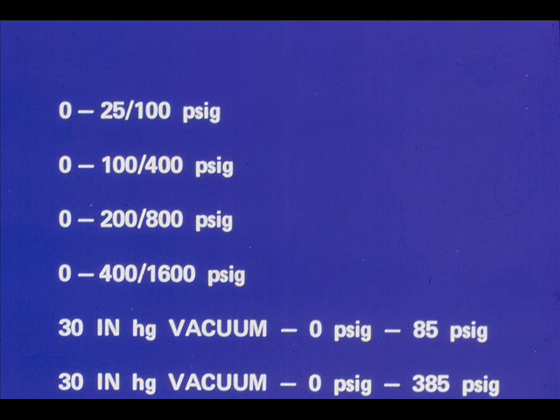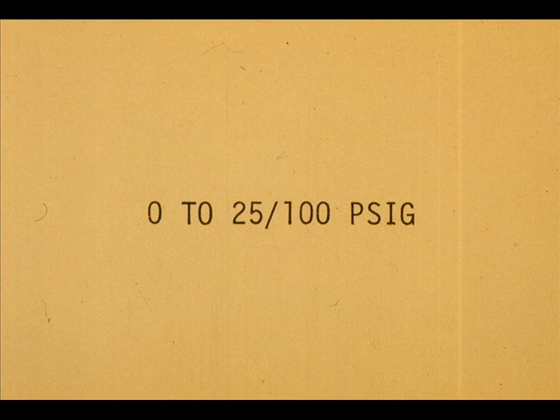The ranges available for the 56PM are shown here. The two numbers give the minimum and maximum range for a given measuring head. For example, the 0 to 25 slant 100 PSIG assembly can be calibrated for a minimum span of 25 and a maximum span of 100 PSIG.